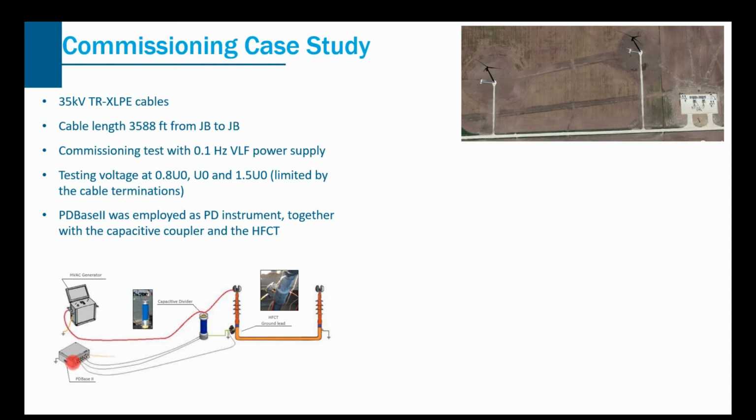And the equipment that we use for this test is the PD Base. This is the one that I talked about for the lab use. This is a very good equipment for the very low frequency PD test.